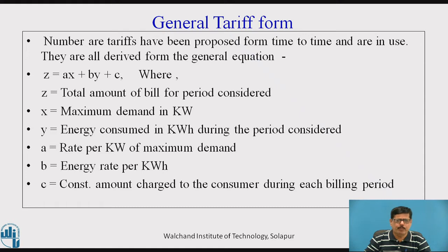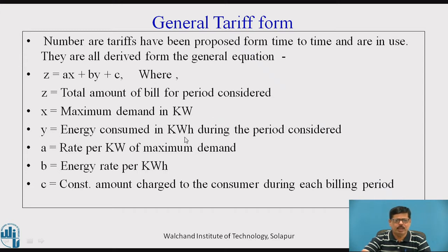Various types of tariffs have been proposed from time to time; however, they are derived from the general equation: Z = AX + BY + C, where Z is the total amount of bill for the period considered (monthly or annual). X is maximum demand in kilowatt, Y is energy consumed in kilowatt-hour during the period, A is the rate per kilowatt of maximum demand, B is the energy rate per kilowatt-hour (per unit), and C is the constant amount charged to the consumer during each billing period.